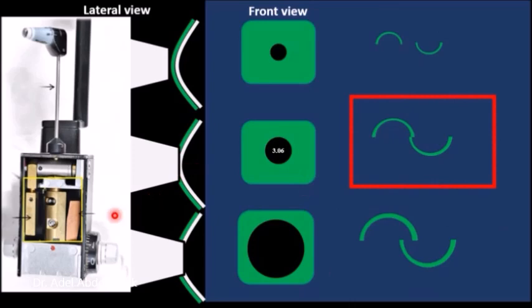Accordingly, the operator will start to rotate this dial. When we change this, we're going to either push the applanation tip in or away from the cornea. So in this case we want to push it more in and in this case we want to push it to the outside till we achieve this appearance. Once we get this appearance, we can have the reading here and this is the IOP of the patient.